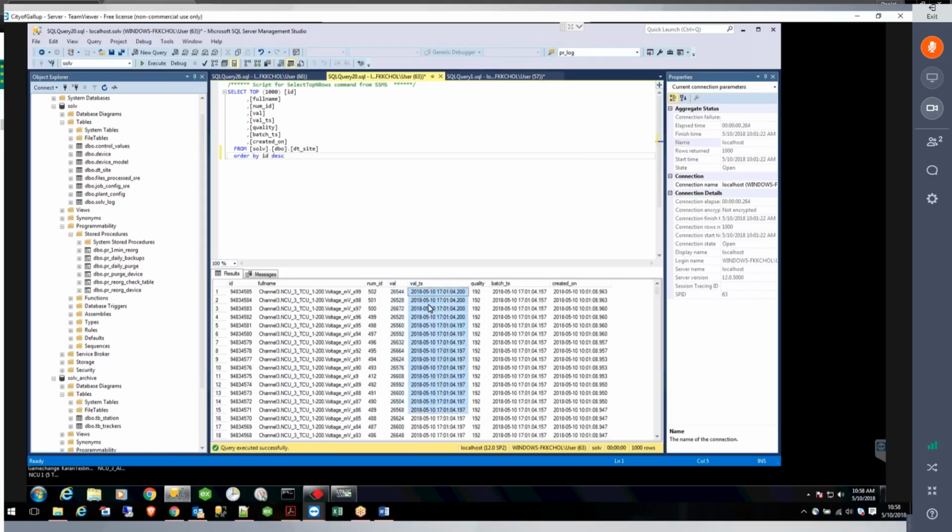This is the value from Kepware, so the value has a timestamp associated with it, and there's also this batch timestamp. The reason we keep both is because this value timestamp, if the device has good quality data and it just hasn't been pulled within a couple minutes, doesn't always update to the right-now time.